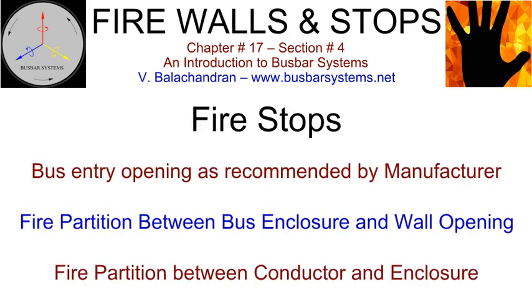Fire stops. An opening with embedment is provided by the project authorities, on the wall, for entry of the enclosed bus. The size of the opening shall be as suggested by the manufacturer of the enclosed bus, and kept to a minimum. To prevent the propagation of fire, the two separate areas must be sealed.